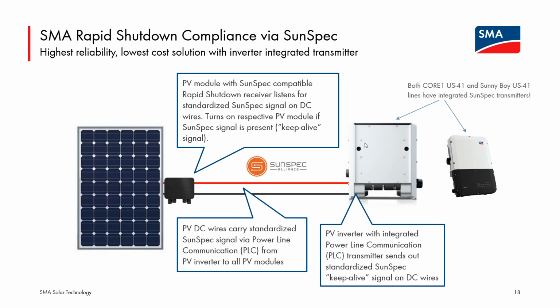When they are turned on during commissioning, they begin to broadcast that keep alive or permission to operate signal. That's what that power line communication signal really is, on the DC conductors between the inverter and the array. So there's no additional communication channel required. That signal is sent out to the array. The SunSpec certified receiver elements will recognize that signal and allow their modules to begin participating in the system, but it will be at the point the SMA inverter dictates via ShadeFix. So these are just on-off devices for their modules, and again, provide code compliance.